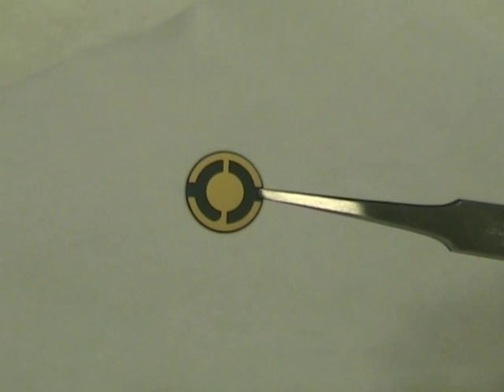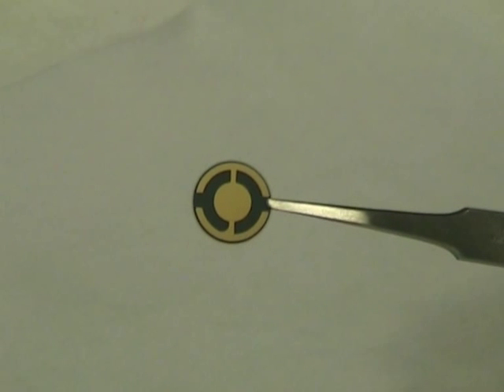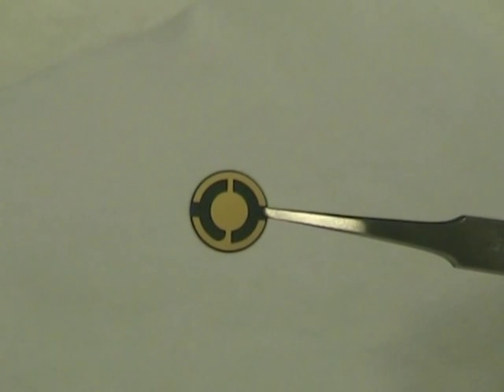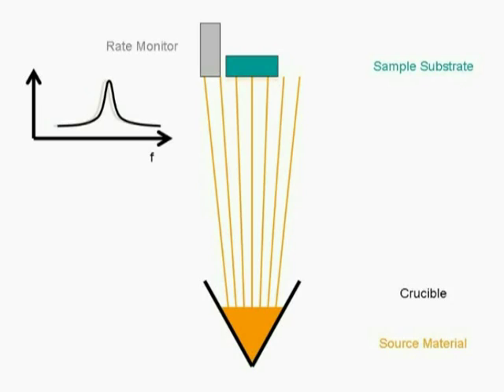The rate monitor is a quartz crystal that can be made to vibrate at a known resonant frequency. As material is deposited on it, the resonant frequency drops. There are relationships between the material properties of the source material — the acoustic impedance and the density — and the change in frequency with thickness.